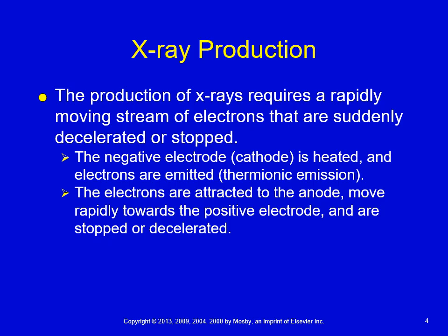All right, the anode of the tube has a positive charge. Just like in real life, how they say opposites attract, the negative electrons that are sitting on the cathode side will be attracted to the positive anode target. Once we do apply the kVp as we're taking the X-ray exposure, those electrons which have that negative charge will fly across at high speeds to interact with the anode target. When they interact with the target, again, they are either slowed down or they are stopped. And in the process of being slowed down or stopped, they will create X-rays.